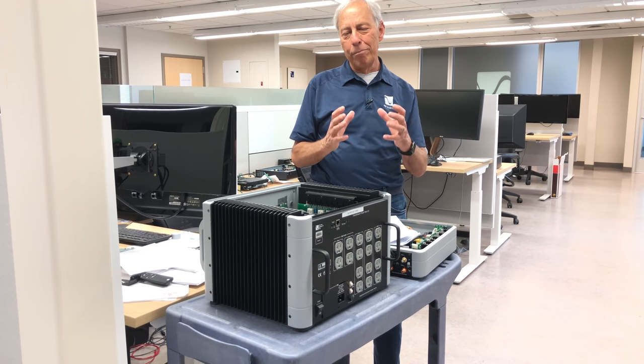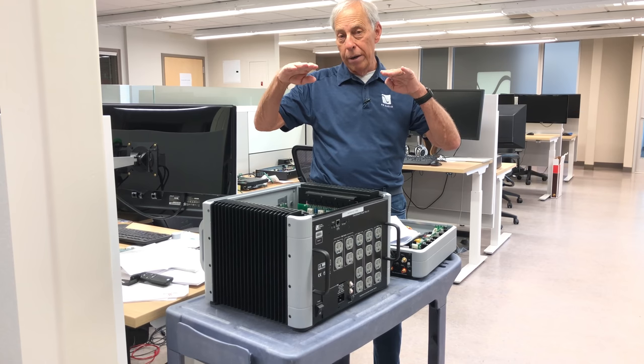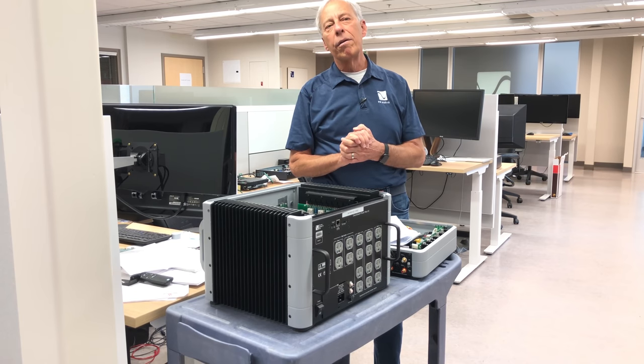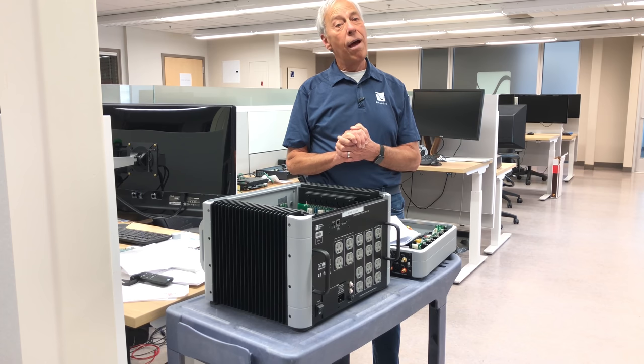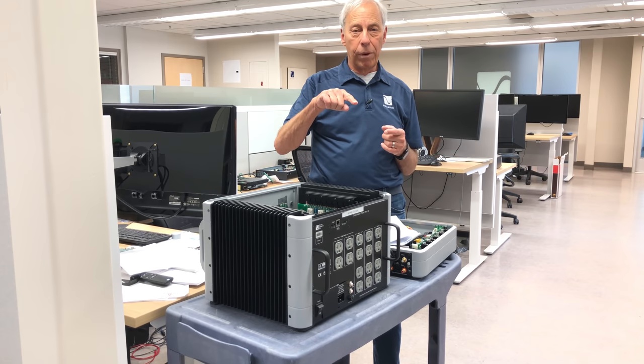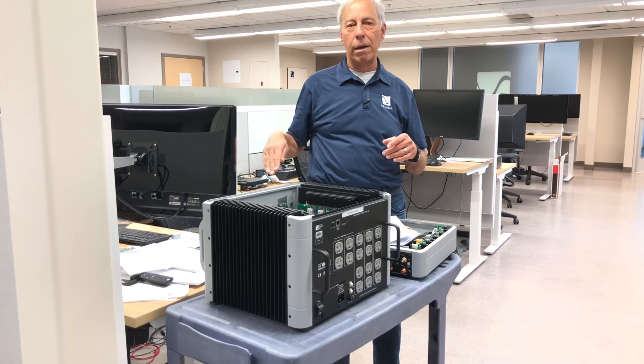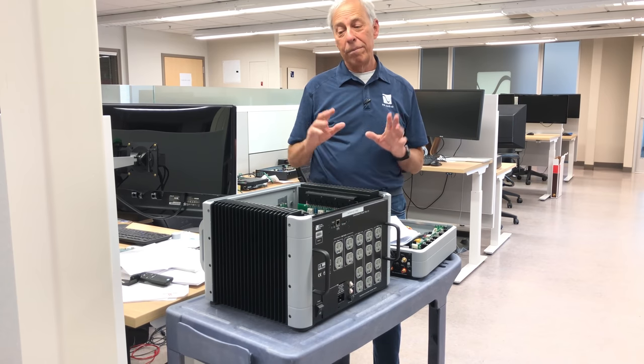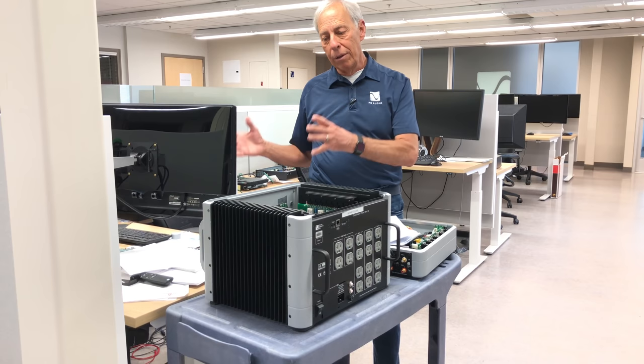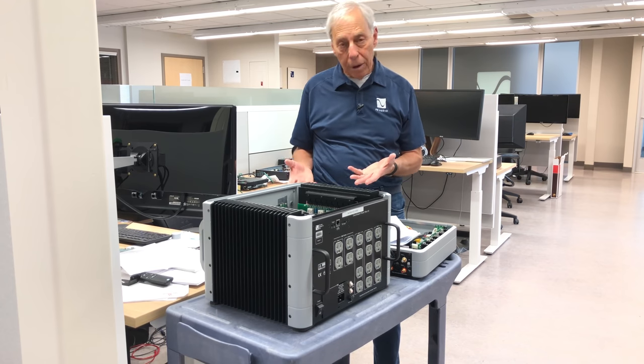In any case, if we have battery voltage, we need to up that voltage and then turn it from DC, direct current, into alternating current, where it's going up and down 60 or 50 times a second. Now, the vast majority of UPSs do this very poorly. In order to save money, because most of them aren't very expensive, they put out what we would call a stepped sine wave, which is basically a series of square waves. And it is ugly, ugly, ugly. But a computer doesn't really care, and you're not going to power it for too long. So those ugly sine waves in the right equipment aren't going to cause any damage, not really a problem. And it only comes on when the power goes off.